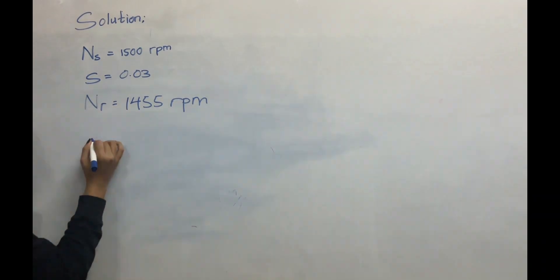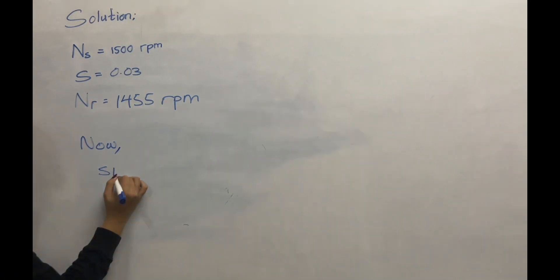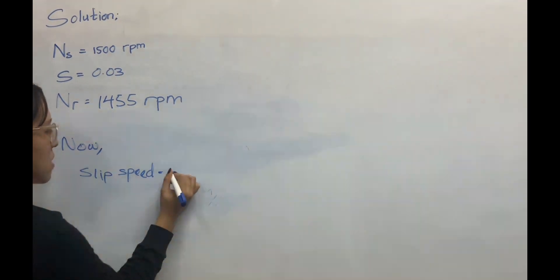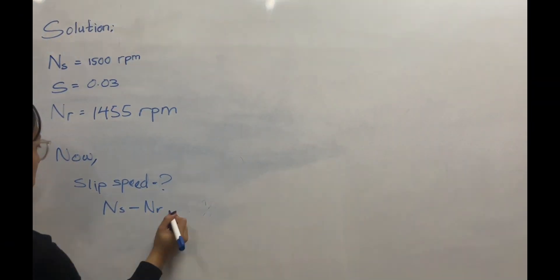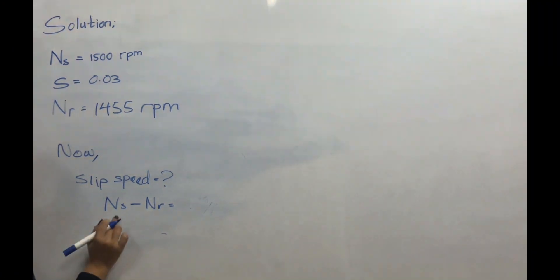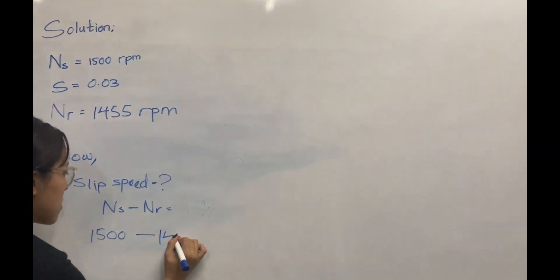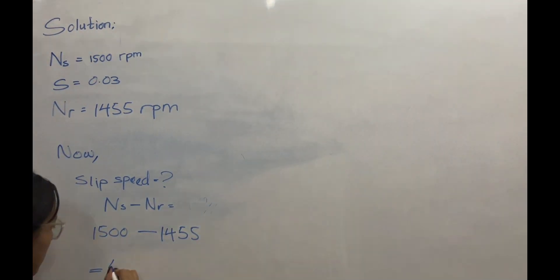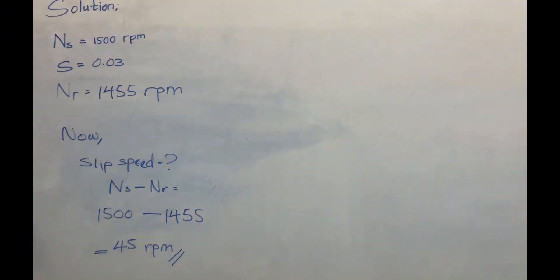Finally, the slip speed is calculated using the formula: slip speed = Ns − Nr. Substituting Ns = 1500 and Nr = 1455, we get the slip speed as 45 RPM. These are all the parameters required by the question. Thank you.